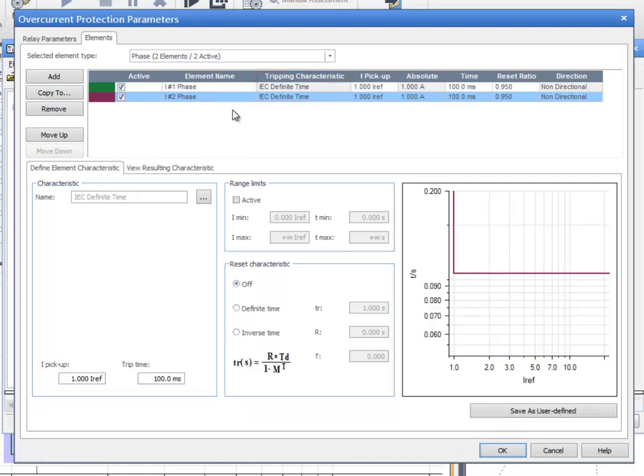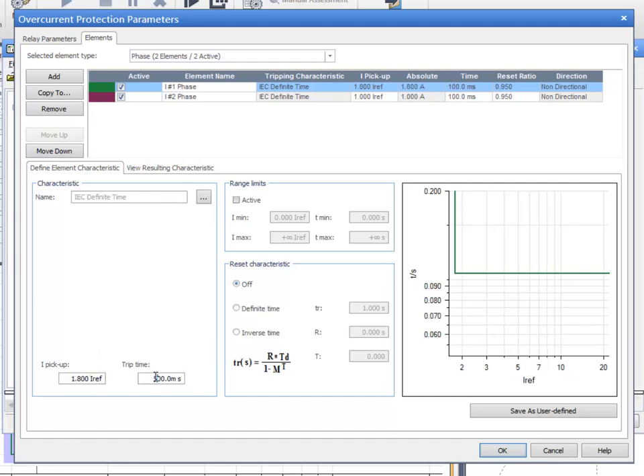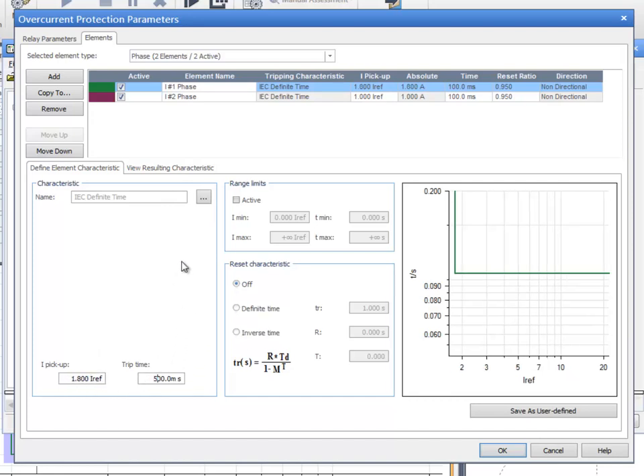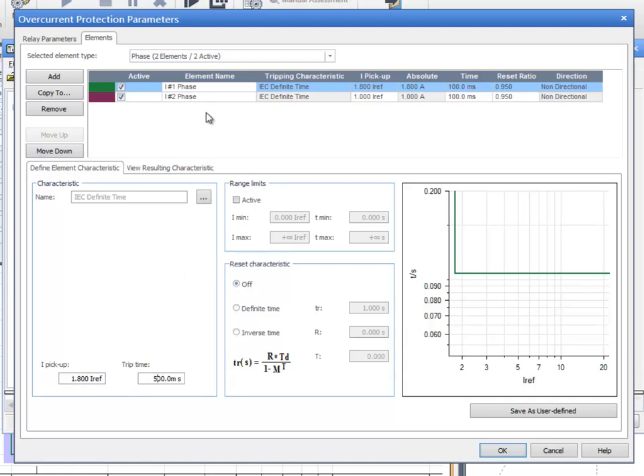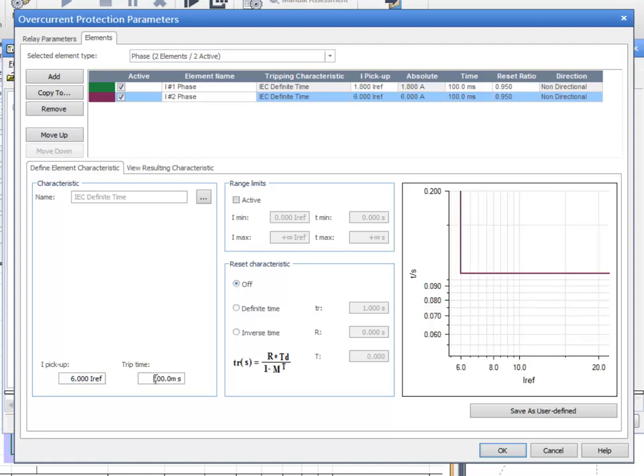The values for the pickup and trip time can be entered for each element. The first element trips at 1.8 amps with a time delay of 500 milliseconds. The second element trips at 6 amps with a time delay of 100 milliseconds. No range limits or reset characteristics are specified.